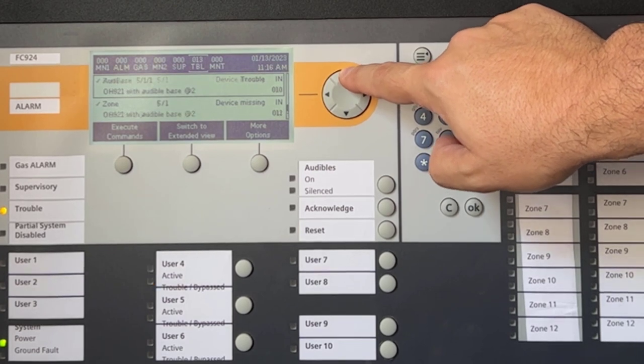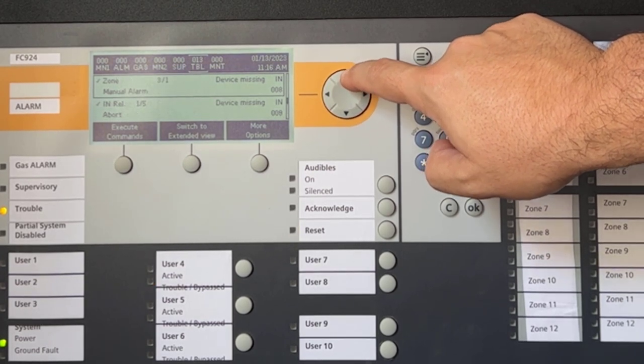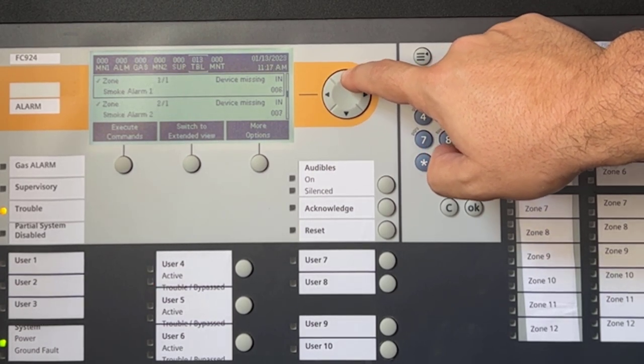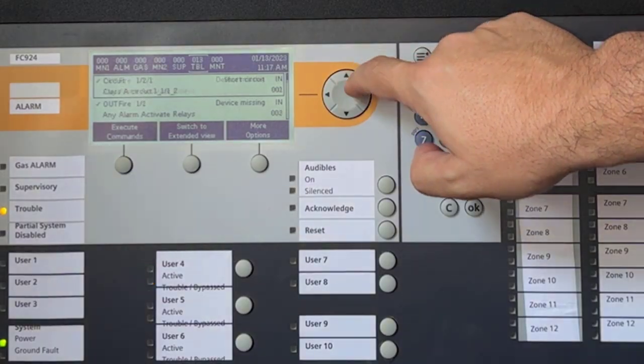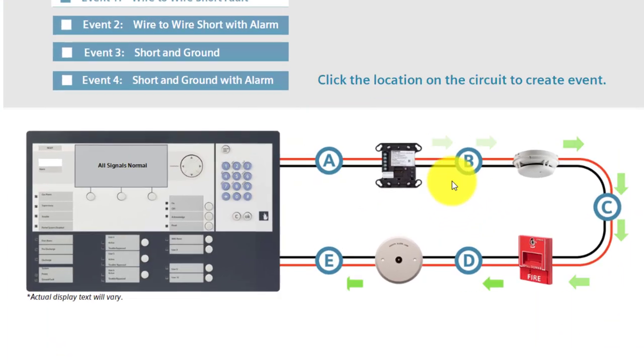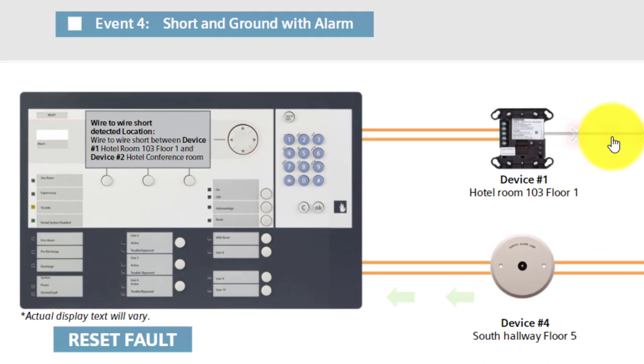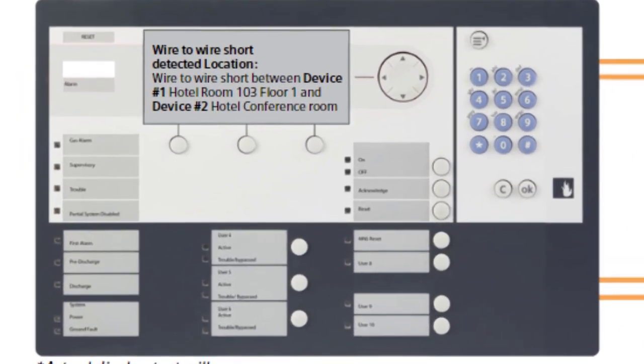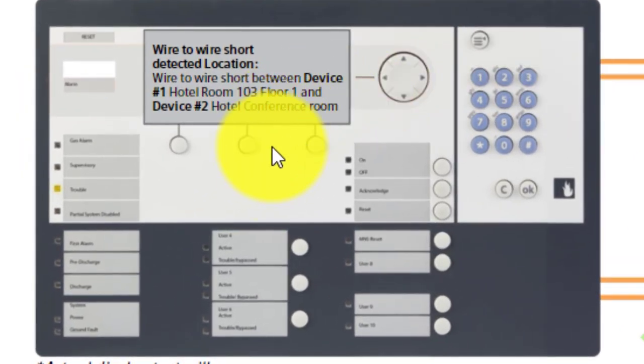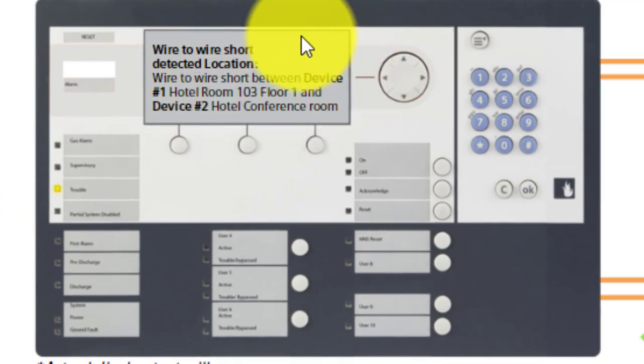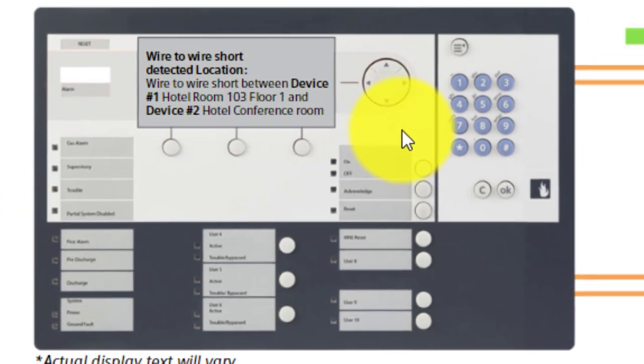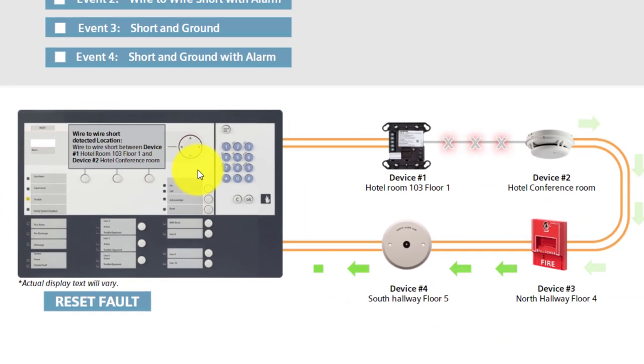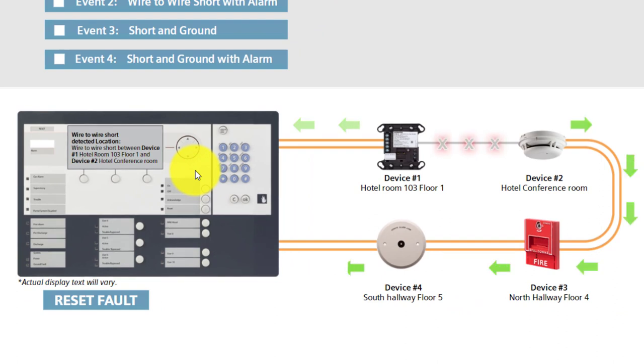For you folks that work in the field, no need to say that it can be a nightmare to pinpoint locations of such condition. By the way, all of our current devices have an awesome technology called ISO Technology, in which the CNET can be installed in a Class X configuration, and a short condition on the loop is pinpointed exactly on the section where it is located, while the system does not lose one single detector. This is really awesome due to its robustness, reliability, time, and cost-saving results. But I will talk more about ISO Technology in a future video.